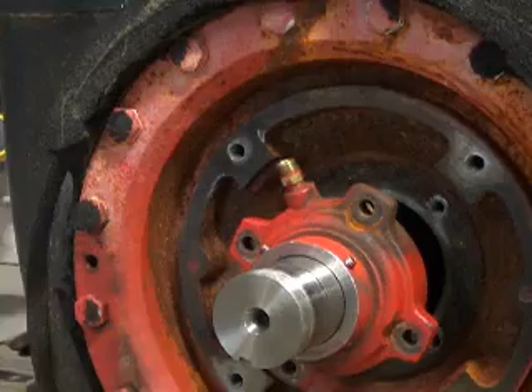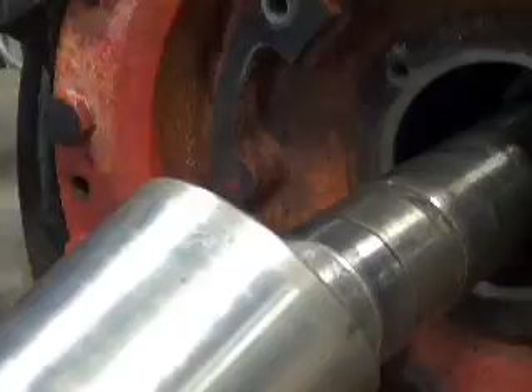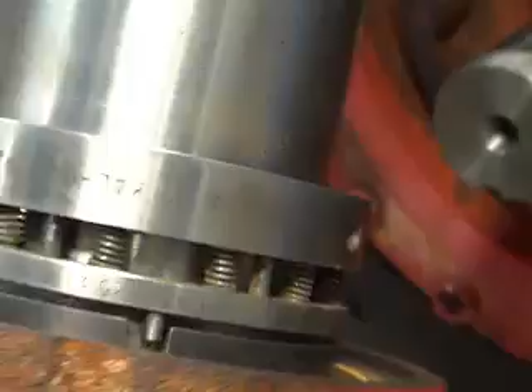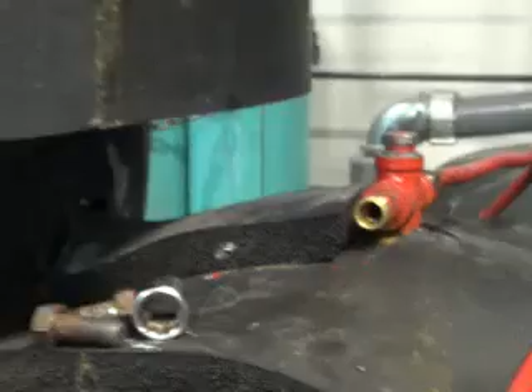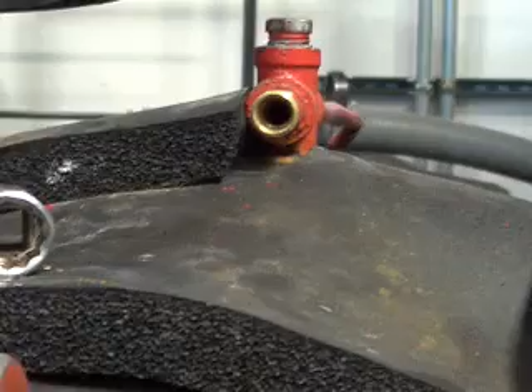I'll have to post some pictures in here from the previous video. This is the old seal, and this is the sleeve. It's an assembly that comes out, and you'll see that the mechanical, the pressure side, is all made out of stainless steel, and there's your springs, but all these springs are on the water side, which I think was the most of my problem. There's a cooling line for this seal that attaches to that brass fitting, and it goes up to the top of the pump. And this pump, by the way, has been in service since about 1998, maybe later, early 2000s, and that fitting was partially blocked with crud.